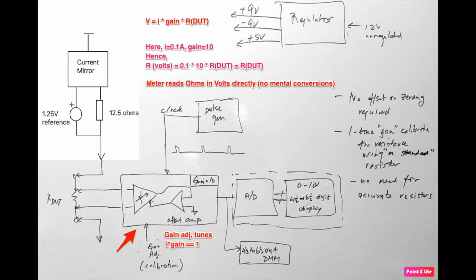Any offsets that are time dependent are cancelled by the offset cancellation circuitry, which is running continuously. So any temperature drift or voltage drift or any power supply related issues are all cancelled. So that's the main advantage of this technique, is you need a single point calibration, and you don't have to worry about zeroing the meter every time you use it.